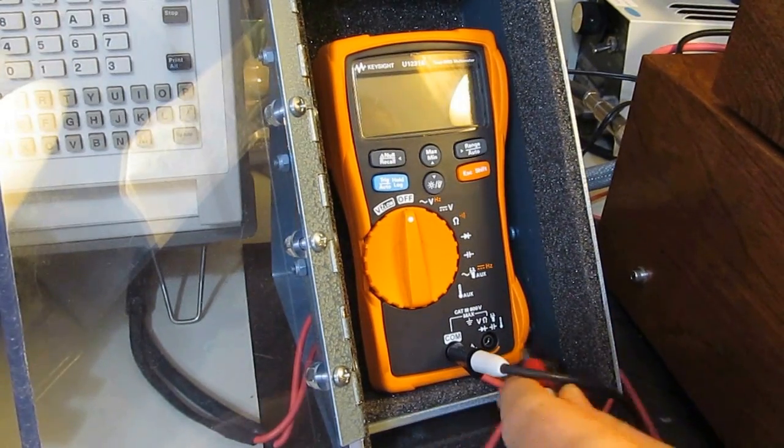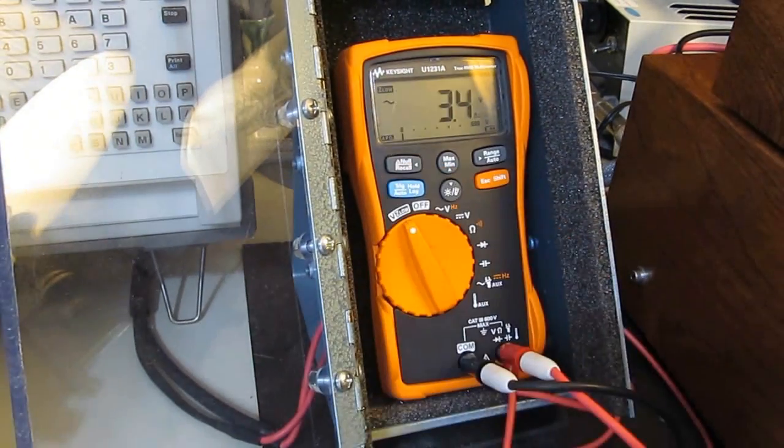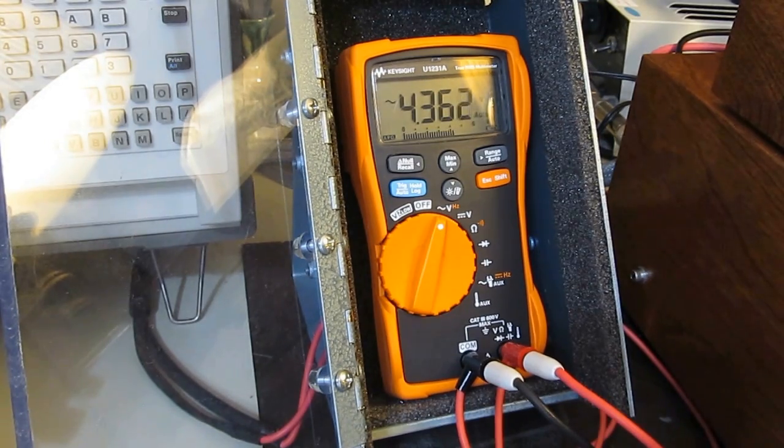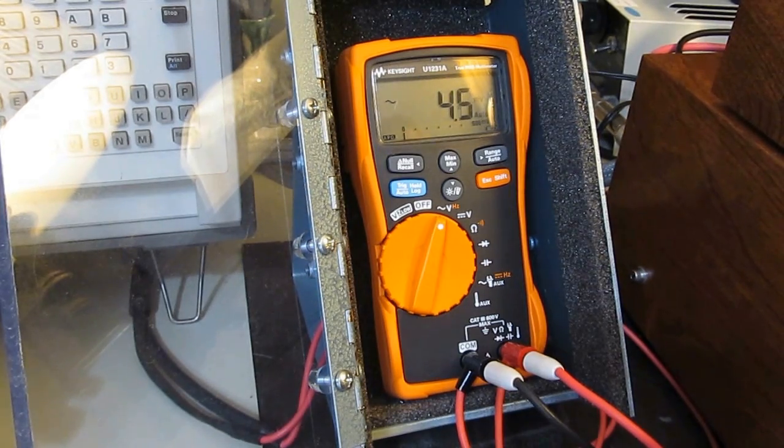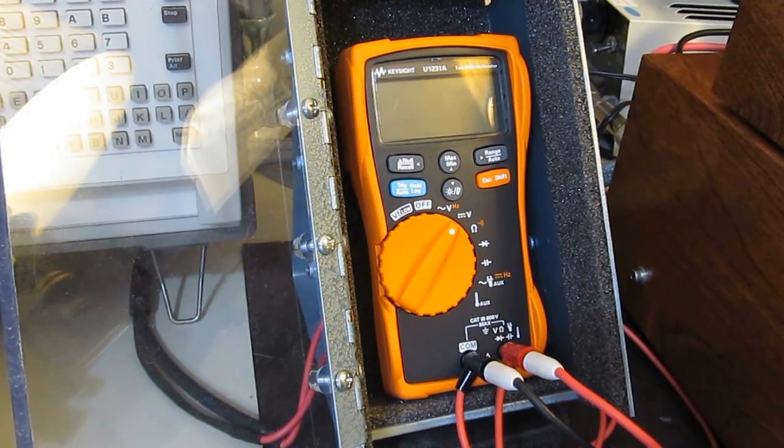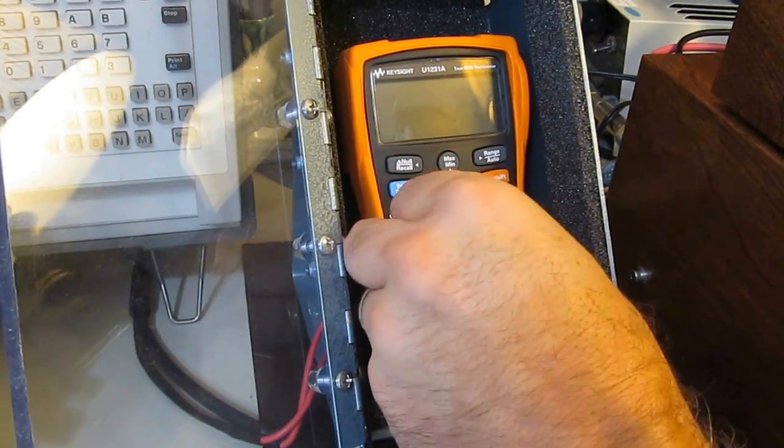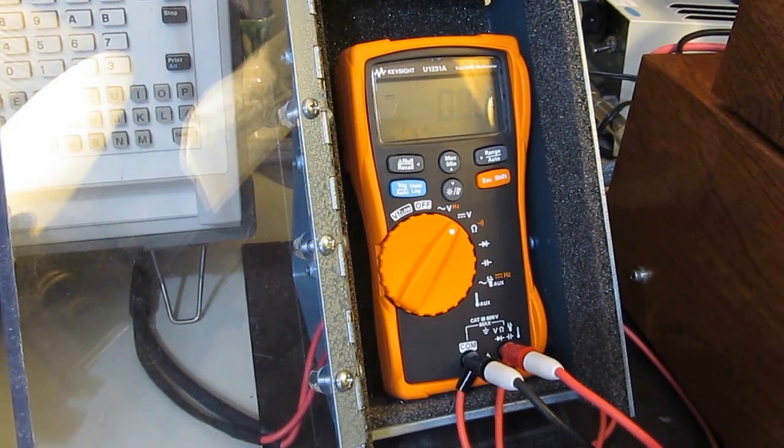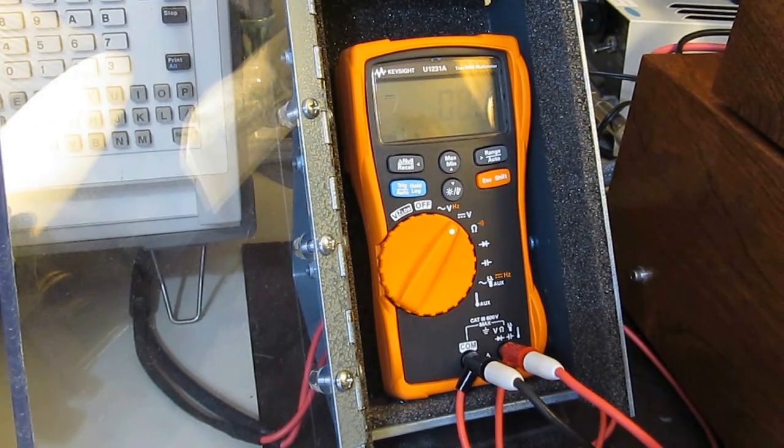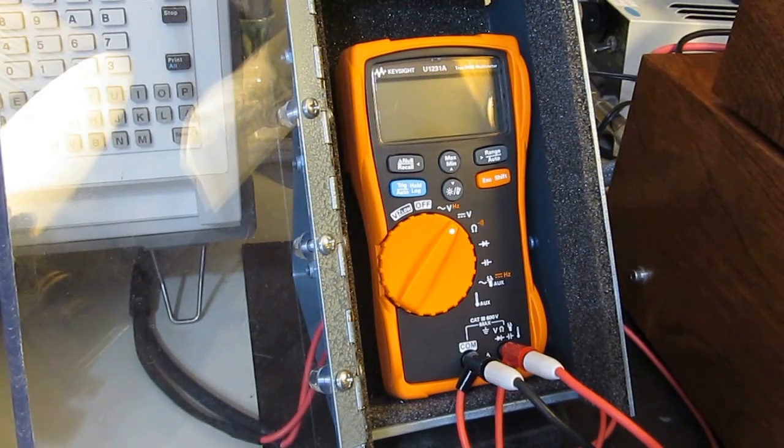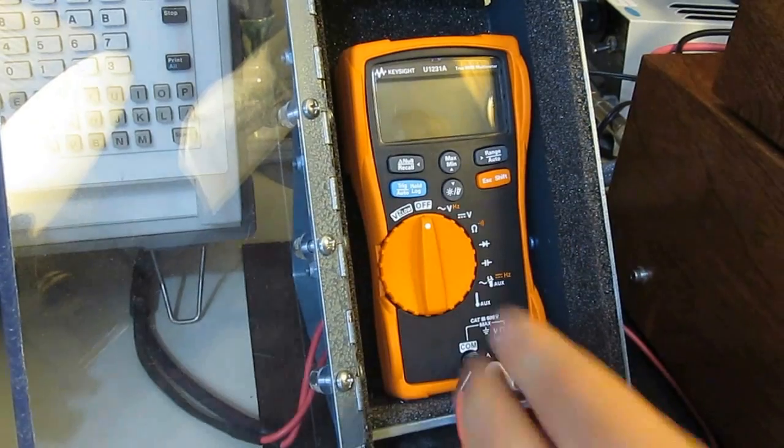Alright, the meter passed the functional test, set it up. This will be five thousand volts. It looks like it reset. Well, it looks like it reset. We'll turn off the generator. Yep, that's it. Meter will not turn on. Well, that's pretty bad, I mean it's only five thousand volts.